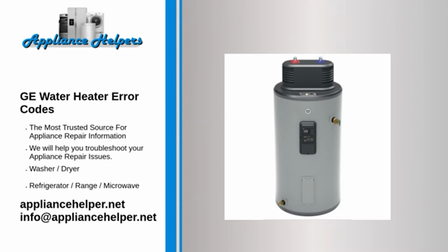Code F4. Problem: fan failure. Fix: disconnect power or unplug the water heater and then check the evaporator for a loose or broken wire connection. If fan motor wiring connections are okay, replace the evaporator fan motor. If the F4 code returns after replacing the evaporator fan, replace the power control board PCB.